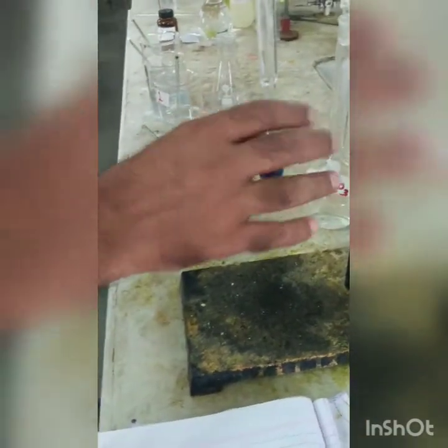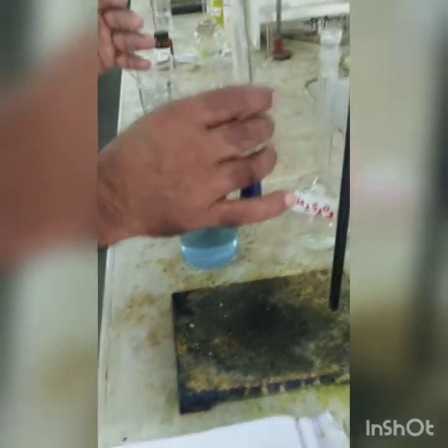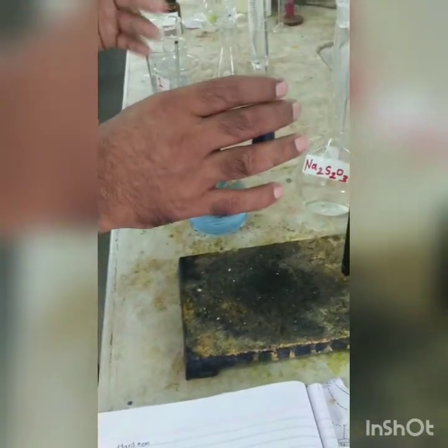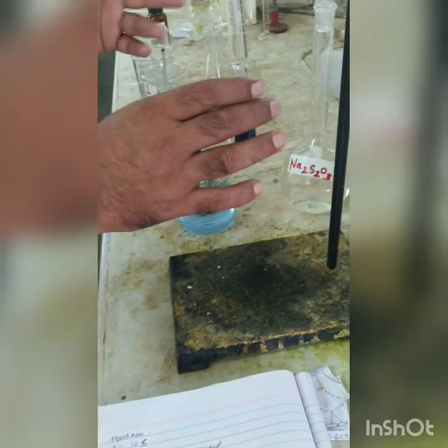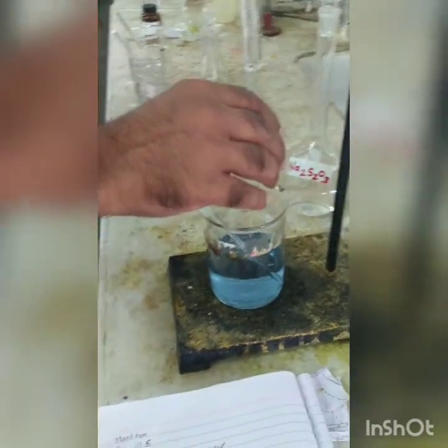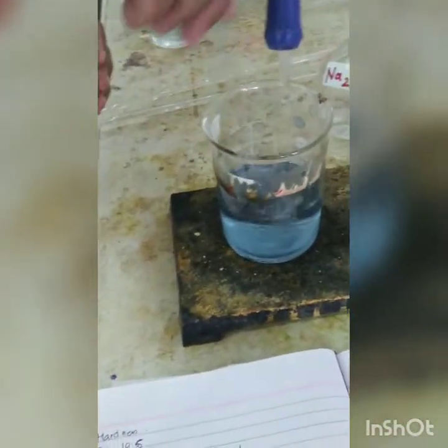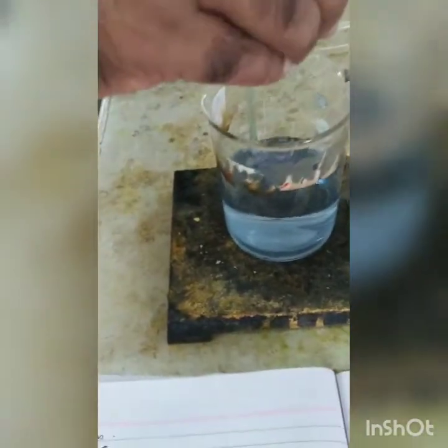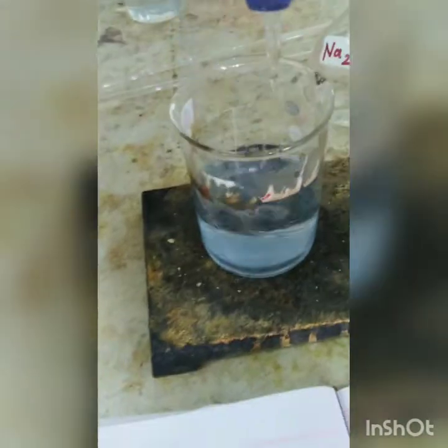So this dosage, which will have a residual chlorine of say 0.5 mg per liter at the water treatment plant, is likely to give a residual chlorine of 0.2 mg per liter at our water tap. Now, if at our house residual chlorine is not 0.2 mg per liter, then that water quality is a suspect. Okay, there could be some bacterial contamination.